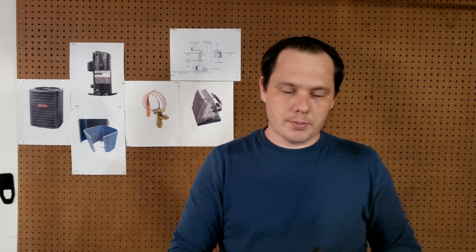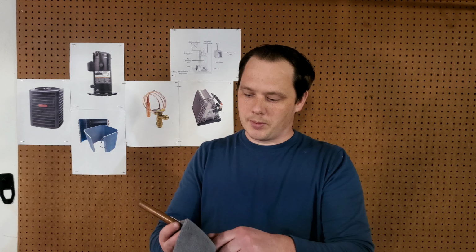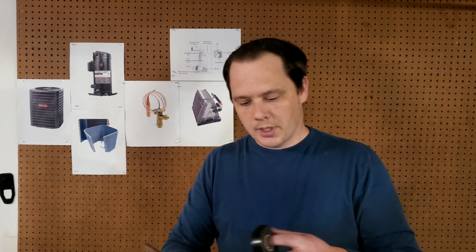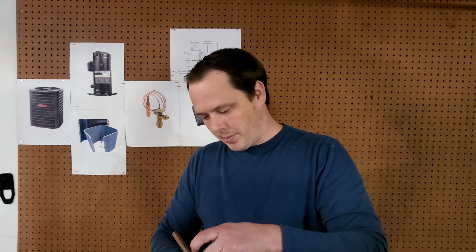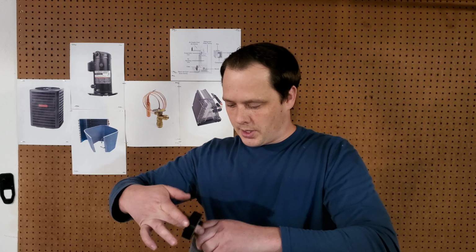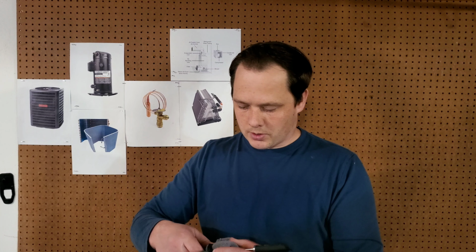So what we're going to do is take an accurate measurement across on each pipe, and then subtract, as I stated before, to find the temperature differential. We're going to take the thermometer, hold it against the pipe, and then we're going to wrap the rag around the thermometer. From there, we have to take some tape and wrap it tightly. Now, if your thermometer is sticking outside of this rag, it's not going to get an accurate reading. So we just pull it back in a little bit and be good to go. The wrap job doesn't have to be pretty, it's just there to create an insulation barrier.